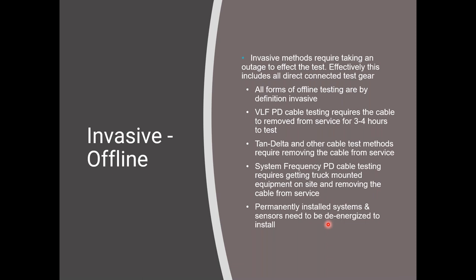Permanently installed systems and sensors need to be de-energized to install. So some of the systems, you can put temporary measurement devices and sensors on. Others, it's maybe more practical to permanently install them. So you're going to have capacitive coupling sensors that go on bus bars, on your motors, on your generators. And it may be more practical to permanently install them and bring the test points out than it is to continuously disconnect, hook up the sensors, run your test, disconnect the sensors, and put the system back to normal. So it may require some permanently installed sensors.